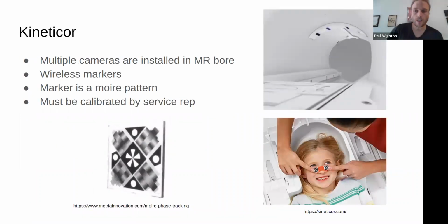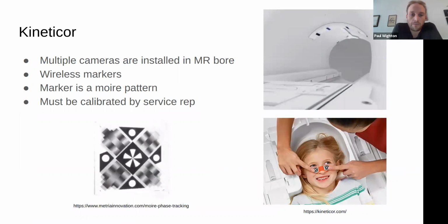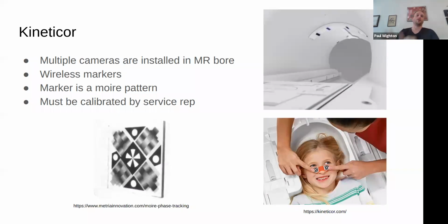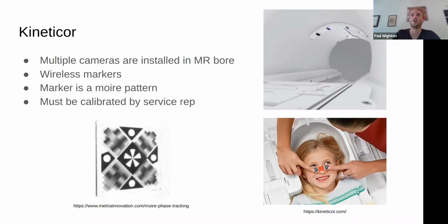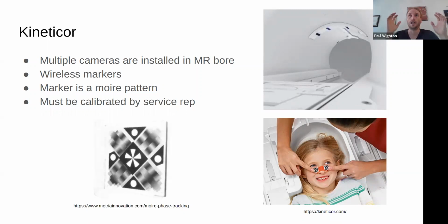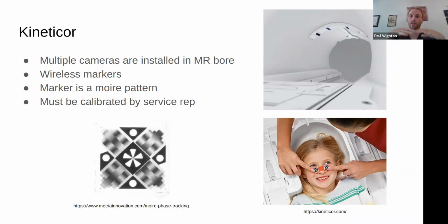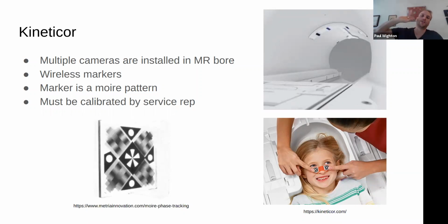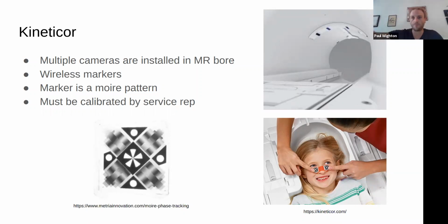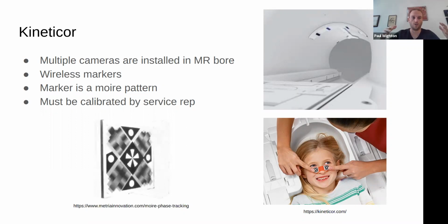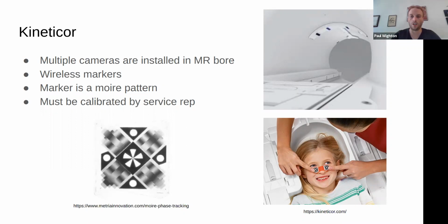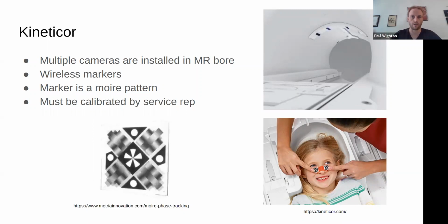Kineticor is one of the big companies that's doing this. So now we're on to optical trackers, and these work by putting either cameras in the bore, or cameras outside the bore with a set of mirrors, and the idea is you're going to optically infer patient motion.